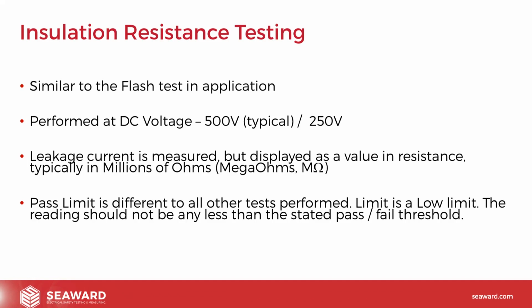However, it is possible to perform the test at 250 volts on many of the devices out there on the market. Particularly the Clare products will perform the test at both 500 volts and 250 volts. The question is, why would you alter the voltage? Well, typically we want to stress the insulation in the most stringent way possible, hence why the flash test is at 1,000 volts plus. So we'd always default to the highest.